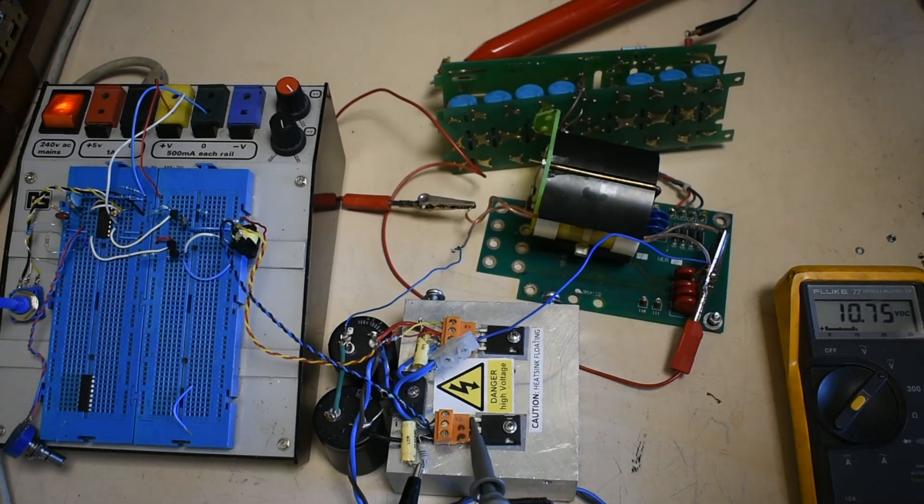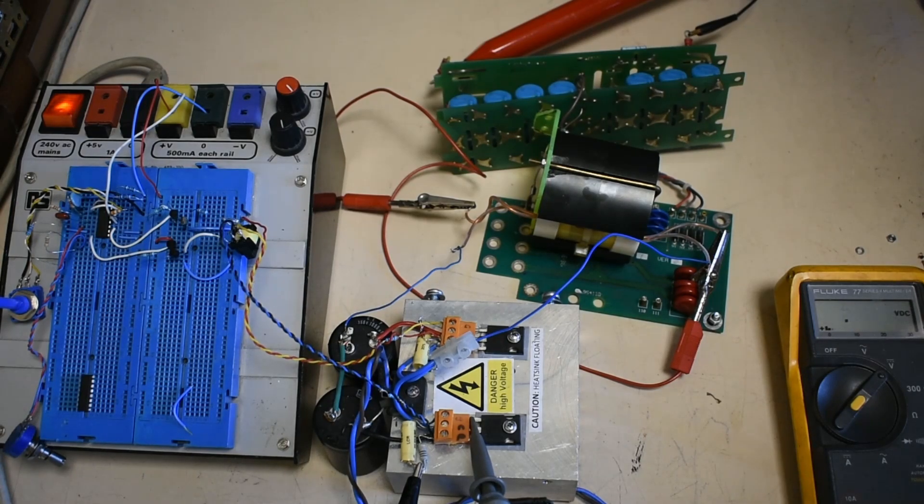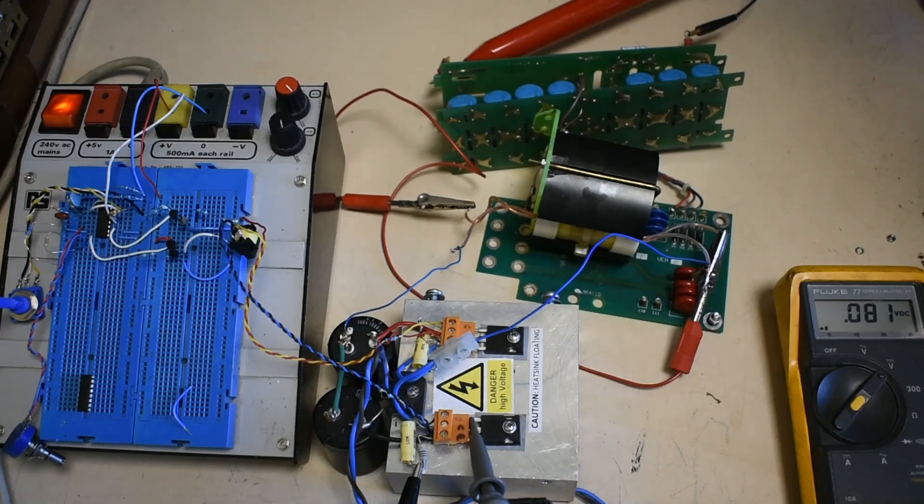If I take the voltage up a bit higher, you can start to hear breakdown. So that's corona developing and I wouldn't want to take it any higher than that. Because of course, I don't want to destroy the transformer.